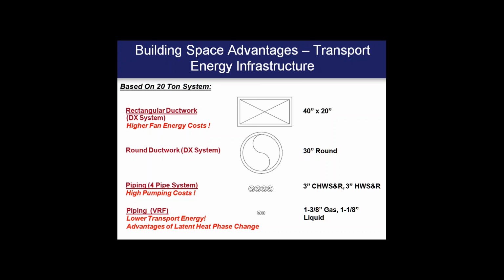You can move into a hydronic system, such as a 4-pipe chilled water, hot water fan coil system, and take advantage of significant space savings, but then you're incurring those high pumping costs associated with that transport energy. So again, moving into VRF, moving that refrigerant medium through the building as a means of transporting energy, taking advantage of that latent heat phase change that's just inherent to the refrigeration cycle. That's always your lowest operating cost and most efficient means of moving energy through a facility.